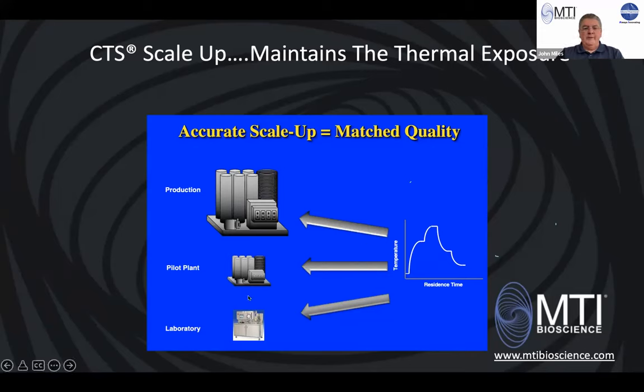Another important point about this is if you're working in the laboratory and you say we need 50 liters of this media, and then 2 days from now somebody says we need 200 liters, it doesn't mean you need a whole new system. You just process longer. A good example is if you have a system that operates at a rate of a liter per minute, in an hour you've processed 60 liters. If you need to get more media, 100 liters, then you run for 100 minutes.